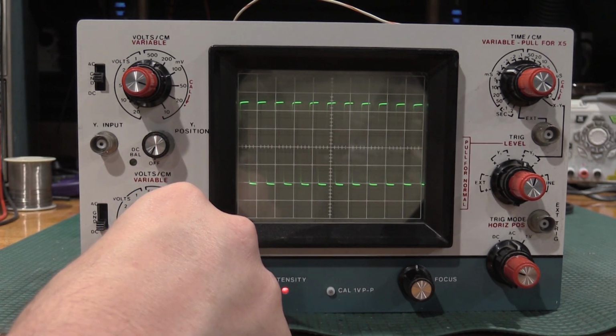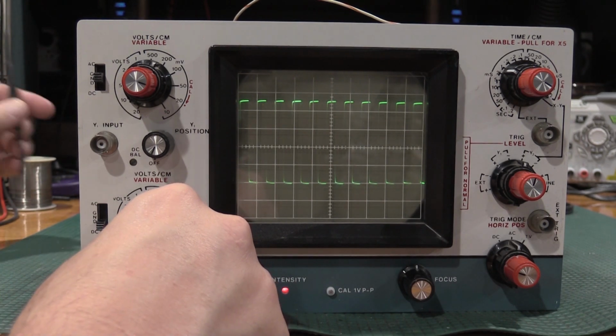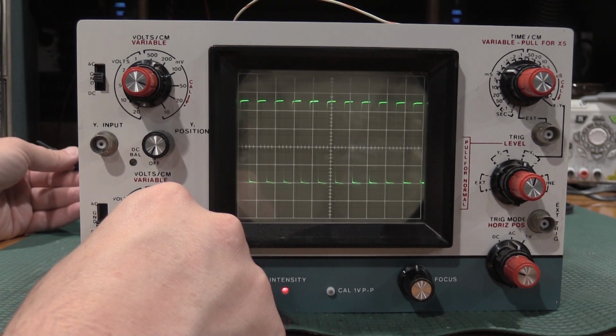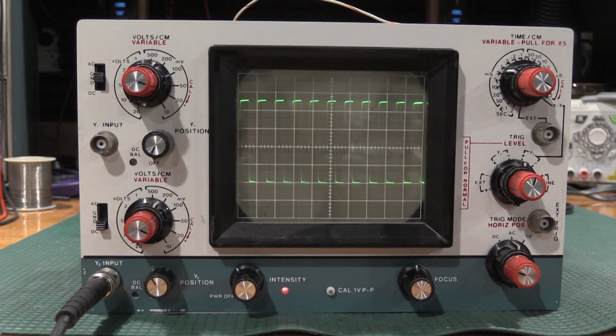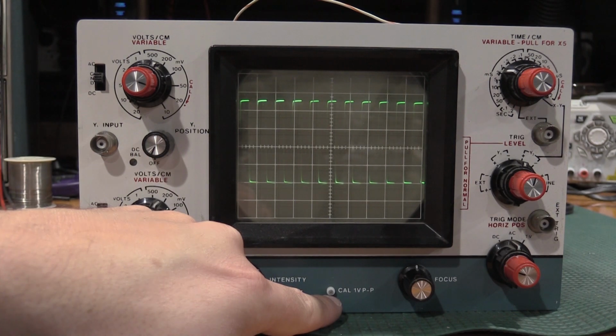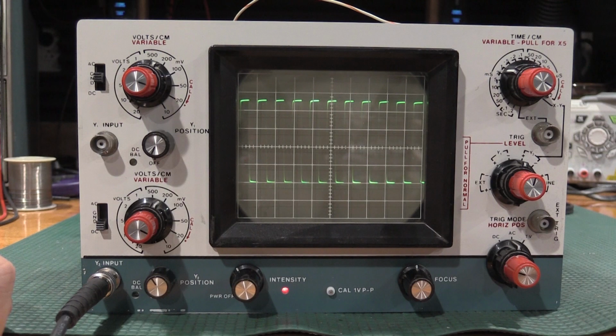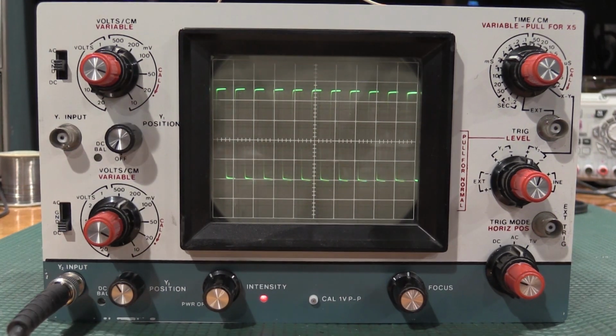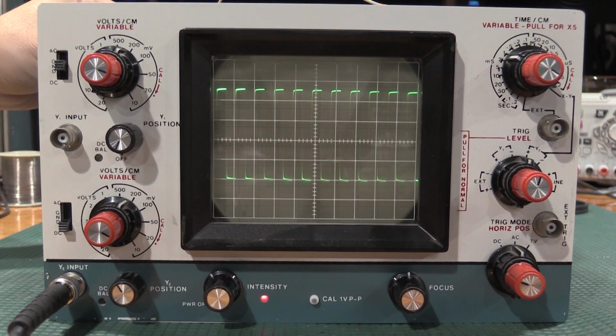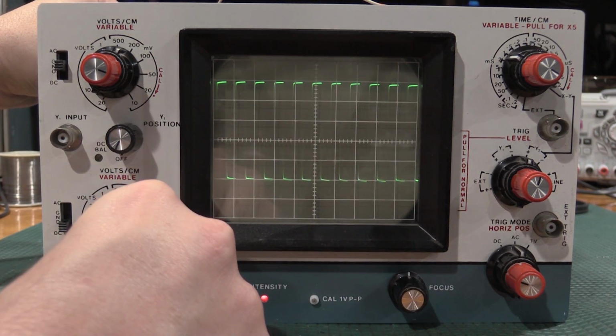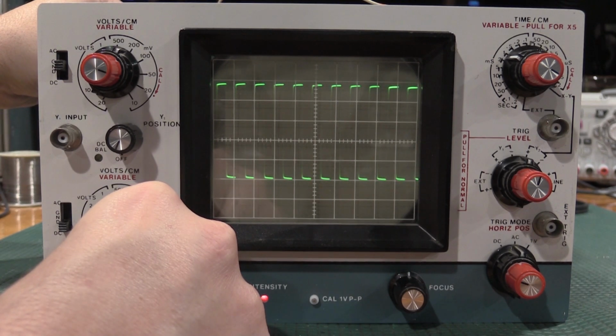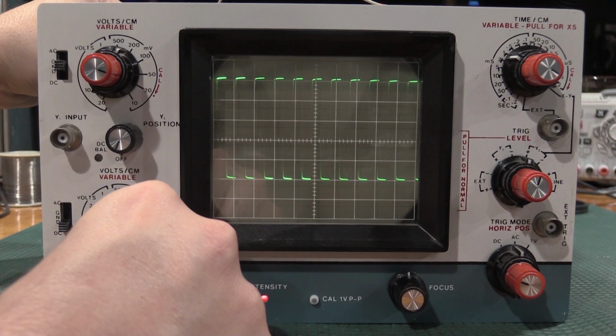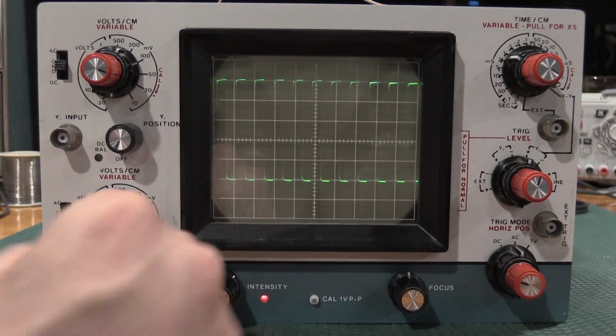Well, this thing hasn't really lost its alignment because they're both off by the same amount. So that probably means that when this was set in the beginning, the standard was wrong. So this hasn't drifted much over the years, but the signal source was off by about 8%. Now, in the book, it tells you to use the 1 volt peak to peak here, which means this was probably off by about 8% when this was initially calibrated. We have much better references available to us here in the lab today than we did when this was assembled originally, which is fine. And there we go. That's our alignment on the verticals.